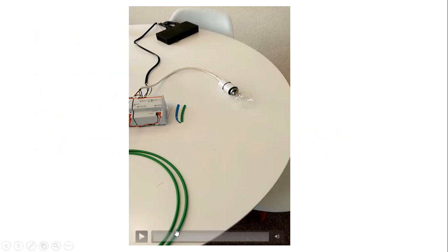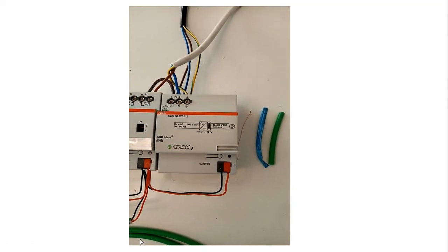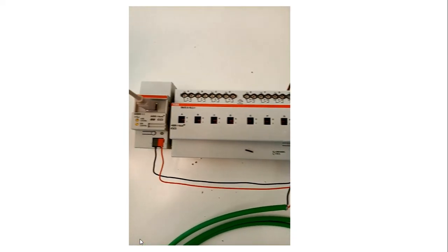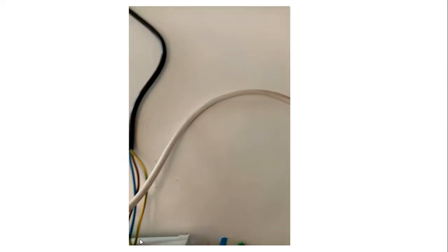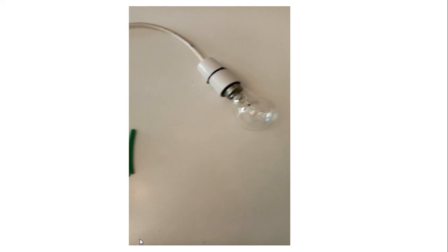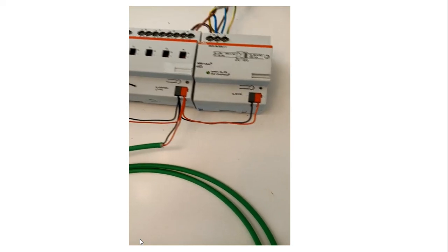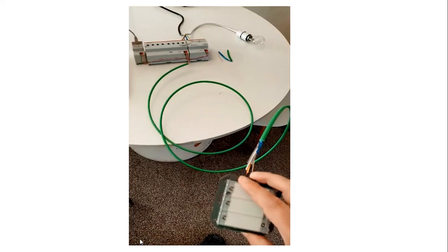Now I have a video showing how the mechanics and wiring work and how you can program it. You can see the red and black cables — this is the power supply, and this is an eight-channel switch actuator which can turn on and off different circuits of lights. This is the KNX cable — KNX works on 29 volts. You can see one cable going from one device to another, and from one device it can branch to three devices.